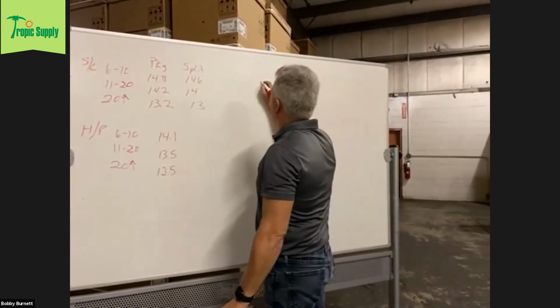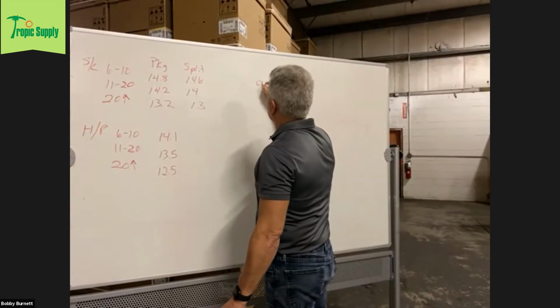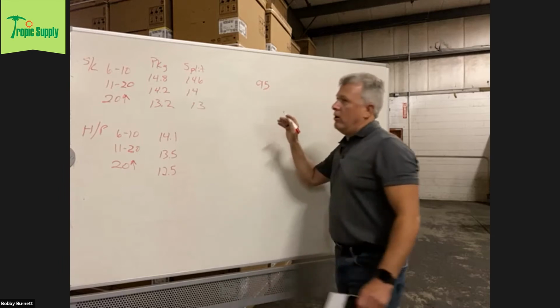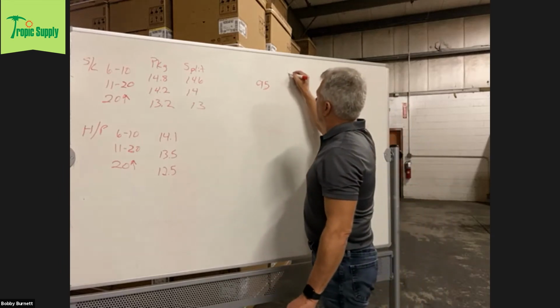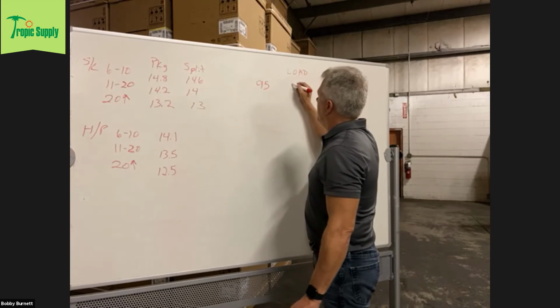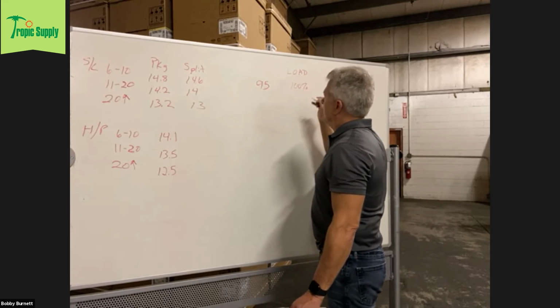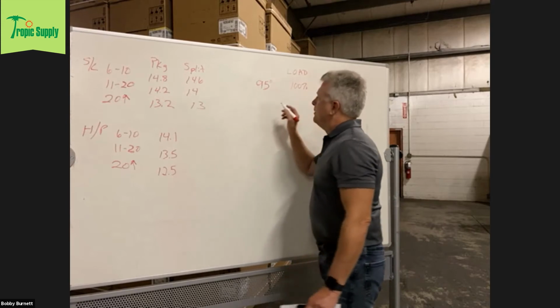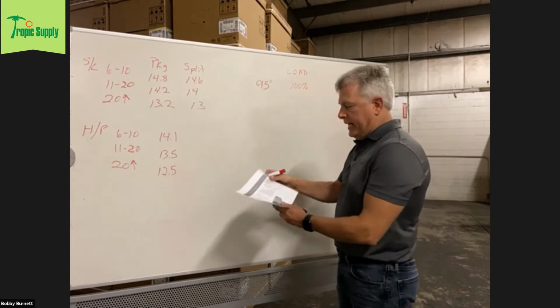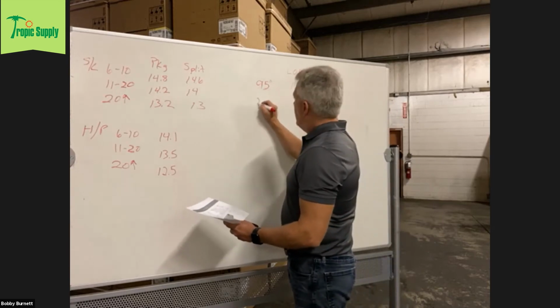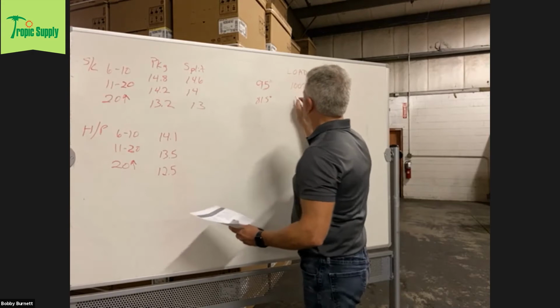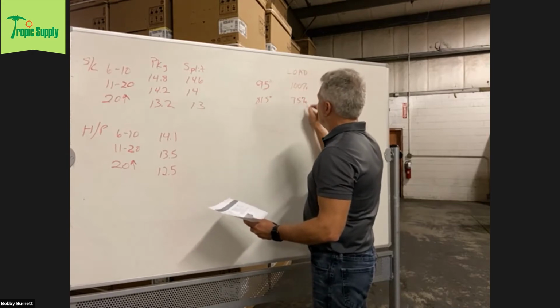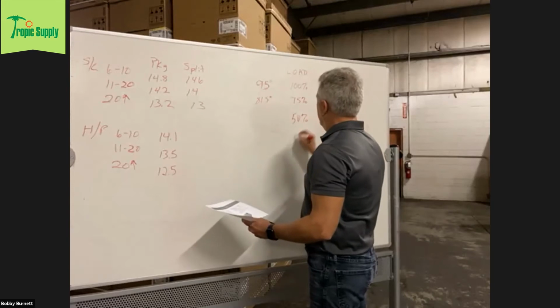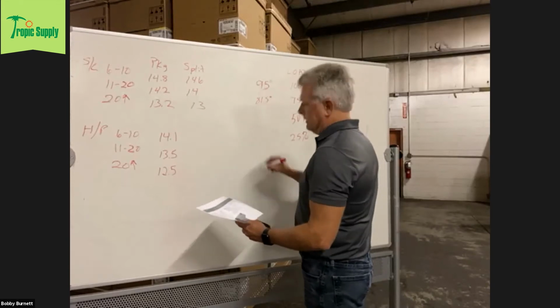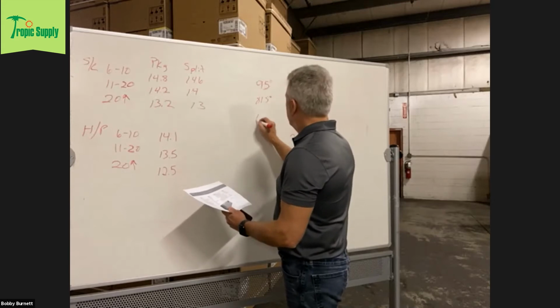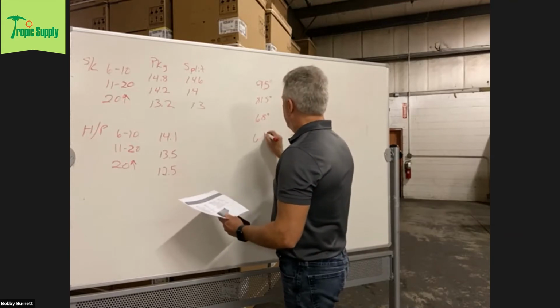Now, the way the IEERs are calculated: remember we had our 95-degree ambient that was pretty much standard in the industry for our rating. That's what they're going to test the first one at, 100% load. Then from there they drop down to a 81.5-degree outdoor ambient at 75% load, then 50% load, 25% load. They go from here to a 68-degree outdoor ambient and a 65-degree outdoor ambient.